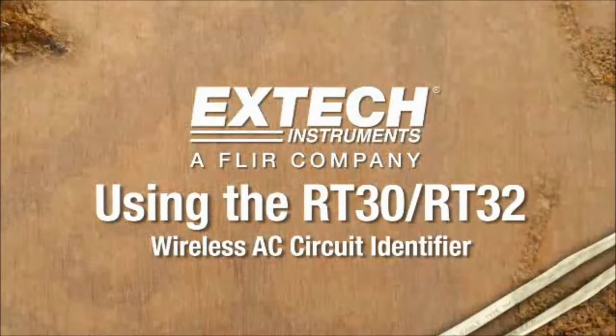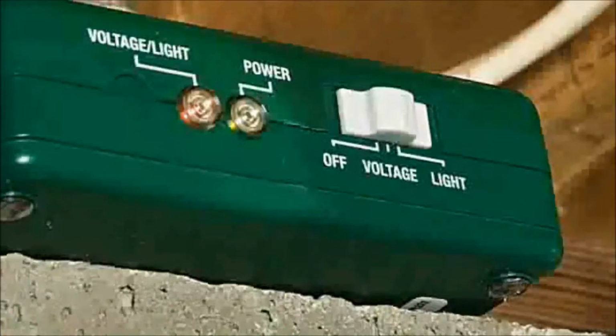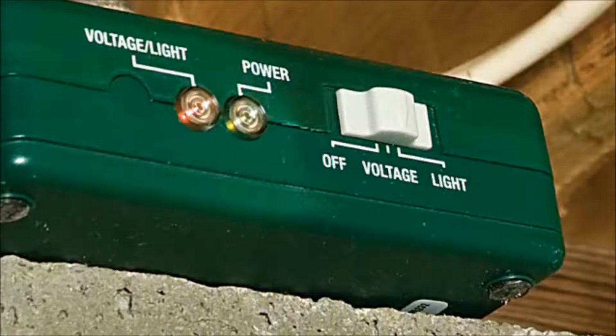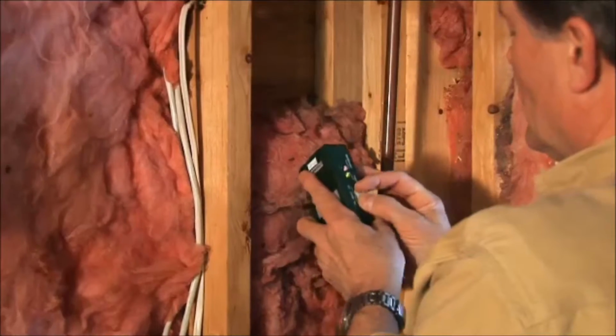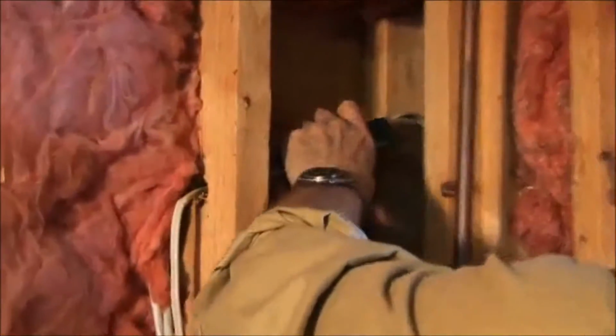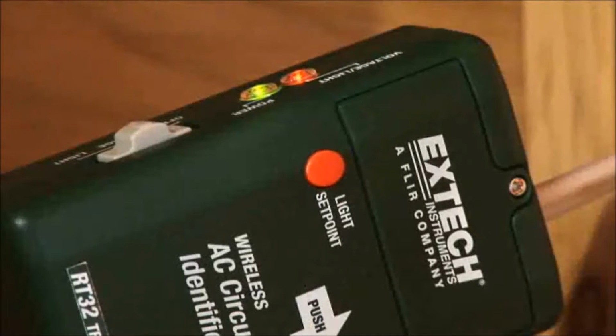Using the RT30 and RT32. Voltage mode. To begin, switch the transmitter to voltage mode. Clamp the transmitter onto the AC cable you would like to identify. If voltage is present, the amber LED on the transmitter will turn on.